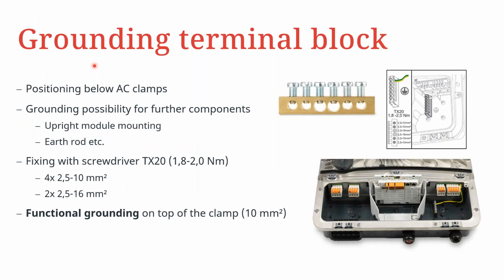The grounding terminal block, as I had said before, is an additional grounding connection for the inverter. But we can see here the functional grounding is actually within the AC connection area, so it can be fitted with a maximum cable of 10 millimeters square. The additional terminal block for grounding can be used for things like earth rods if you want to connect directly. And here you have the possibility to connect cables up to 16 millimeters square. So this is just an additional option.